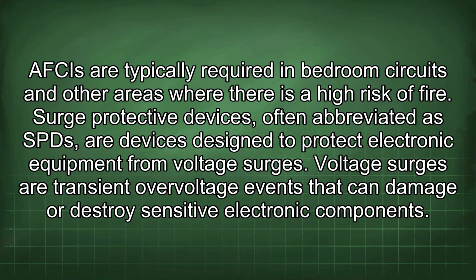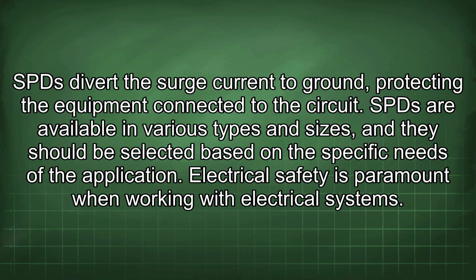Surge protective devices, often abbreviated as SPD, are devices designed to protect electronic equipment from voltage surges. Voltage surges are transient over-voltage events that can damage or destroy sensitive electronic components. SPDs divert the surge current to ground, protecting the equipment connected to the circuit. SPDs are available in various types and sizes, and they should be selected based on the specific needs of the application.